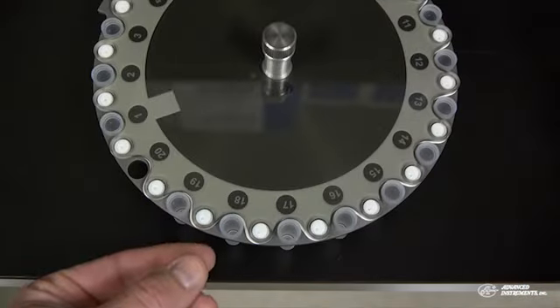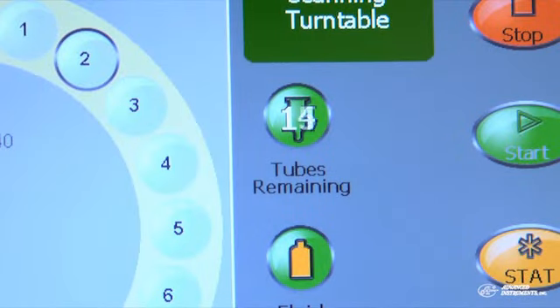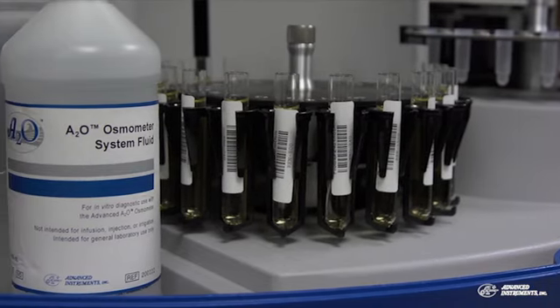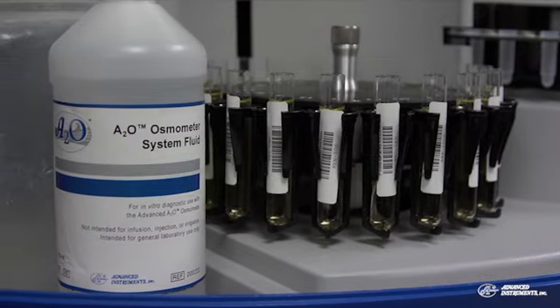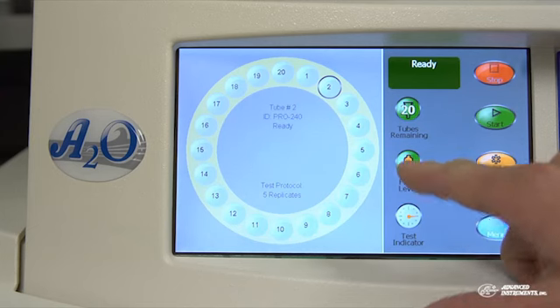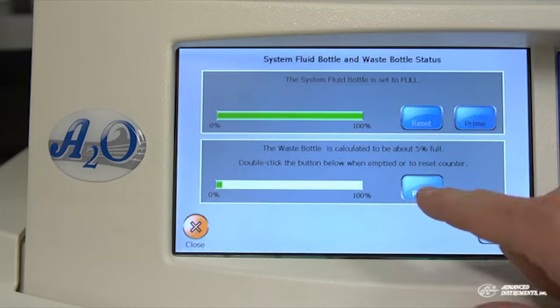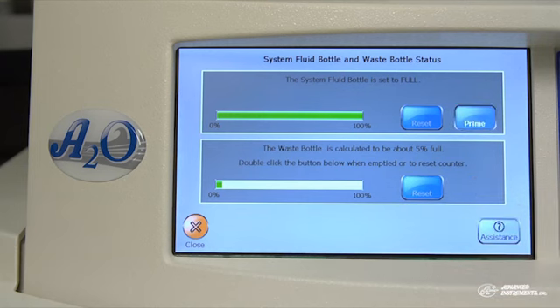The osmometer carousel holds up to 20 sample cups. The A2O software keeps track of the number of clean sample cups remaining and will alert the operator when it is time to load replacement cups. The fluid management system automatically cleans the pipette after each sample to prevent carryover and cross-contamination. The A2O system fluid and waste levels are monitored through software control, making it easy to know when fluid replacement is required.